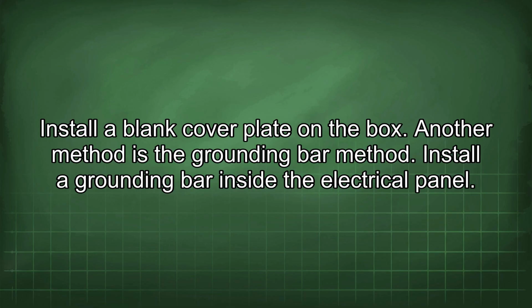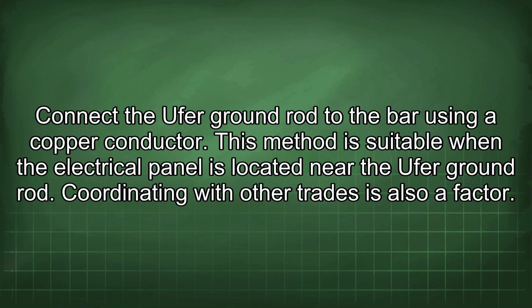Another method is the grounding bar method. Install a grounding bar inside the electrical panel. Connect the Ufer ground rod to the bar using a copper conductor. This method is suitable when the electrical panel is located near the Ufer ground rod.